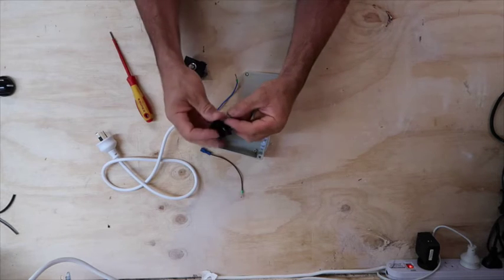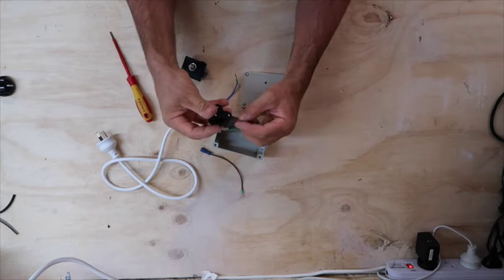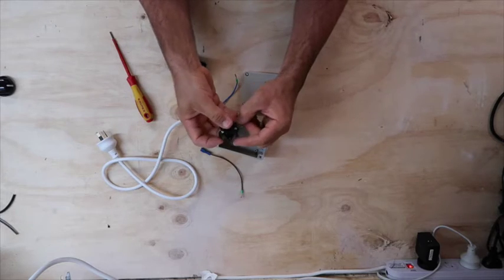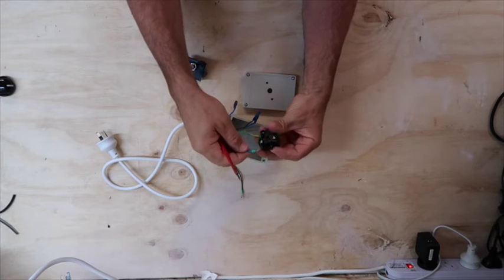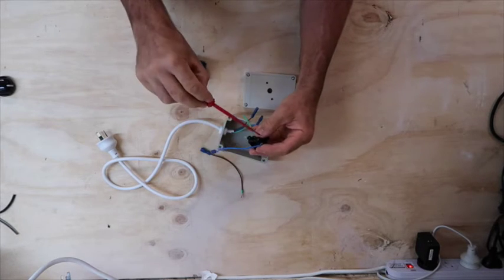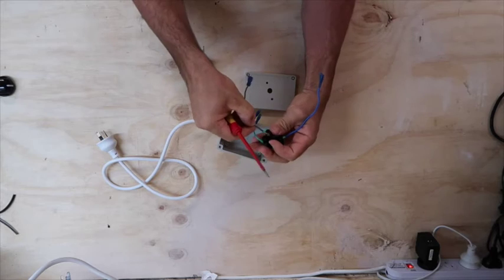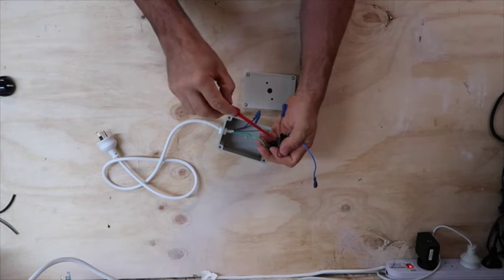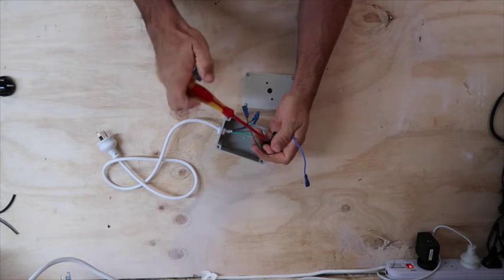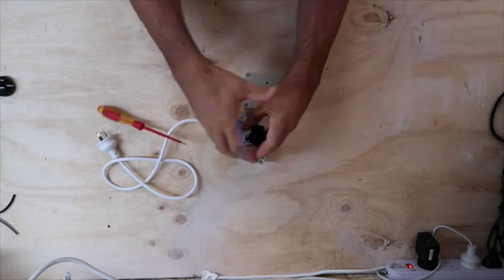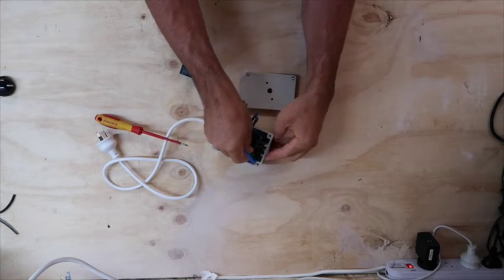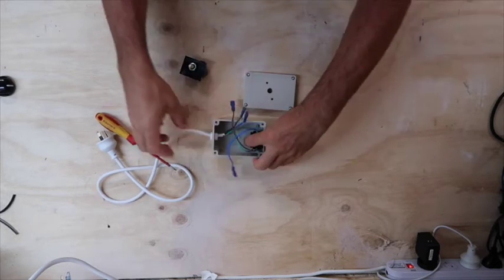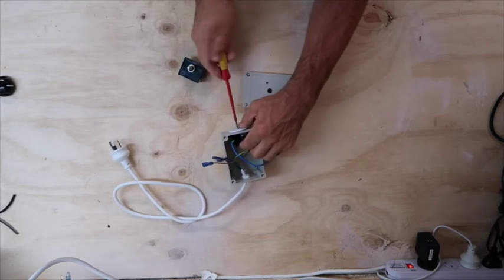So we'll attach these cables now, and screw the terminal on the back of the powerpoint. So the earth goes straight through, then blue goes to neutral. The brown goes to active. And that screws onto the back of the fitting.